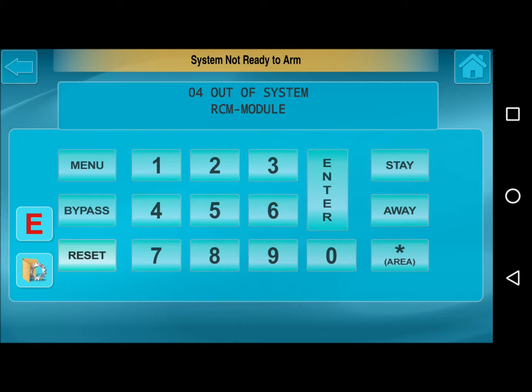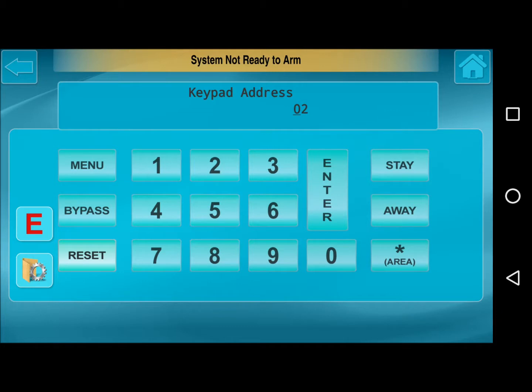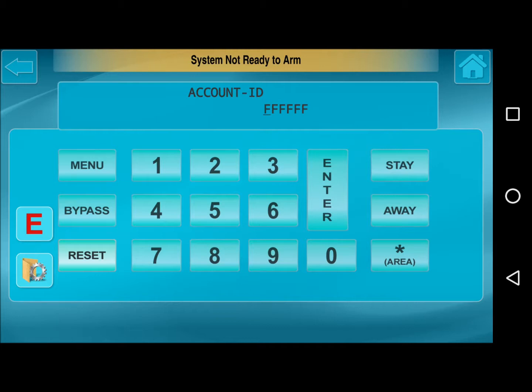To get into keypad configuration, enter 1-1-1-2-3 then Menu. We're going to press Menu or Function to toggle through until we see the keypad address. In this demonstration, we're going to be changing it to 02, so we just type in 02 and then press Enter or On/Off to save it. Once that's done, we can press Menu or Function to keep toggling. We're just changing the keypad address and the keypad type — any other information we see in here we're not concerned with.